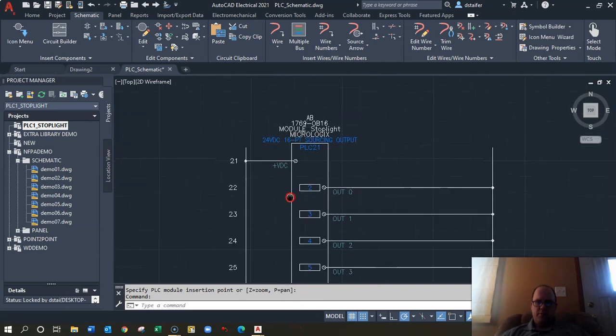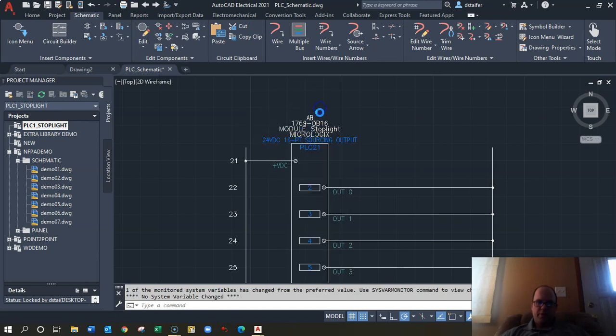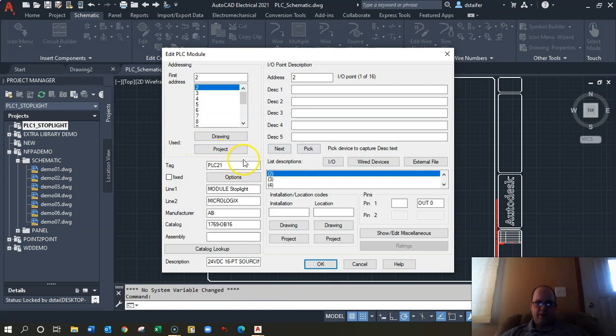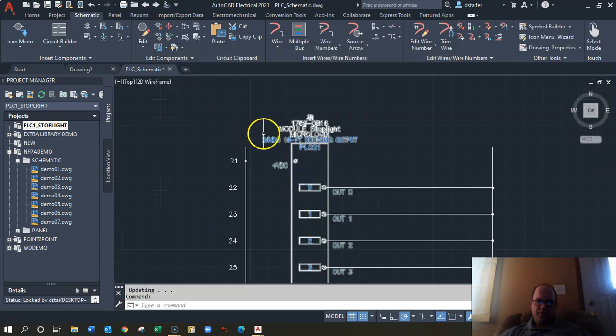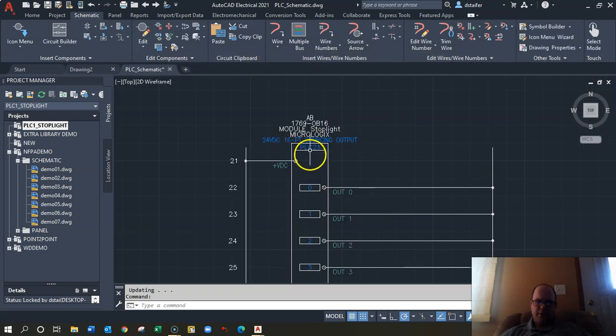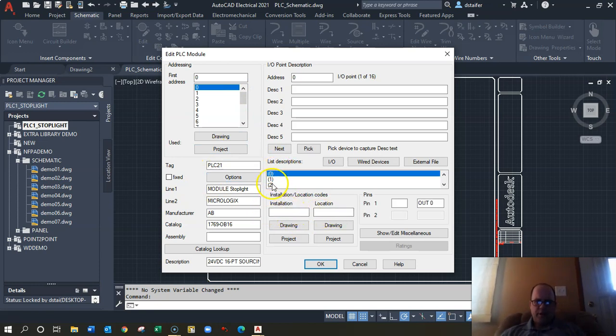Again it says Micrologix — right-click on here and edit the component to call it CompactLogix. Also, I should set the first address to zero since it's the first address of the card. That's easy to fix — Out:0. You can also right-click on a component and change the slot number and other location information.